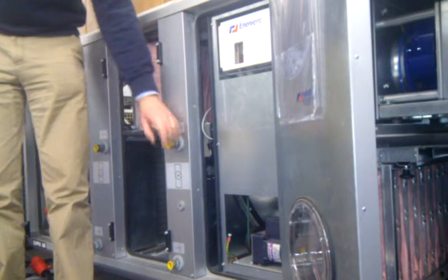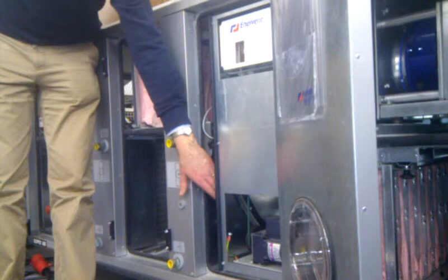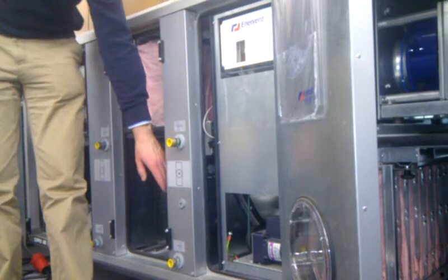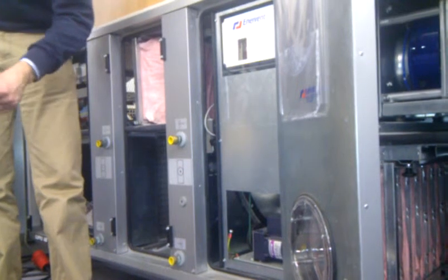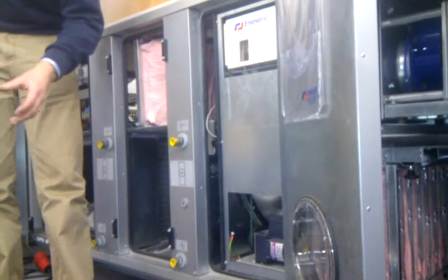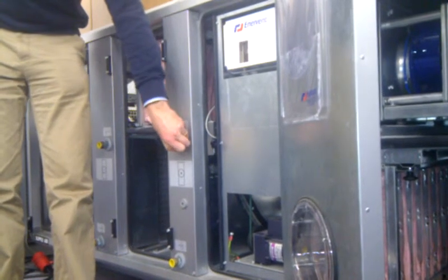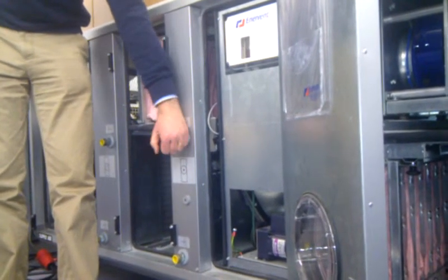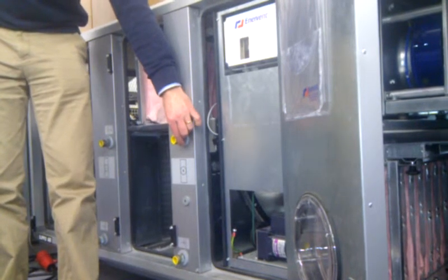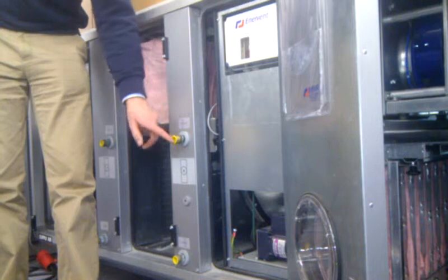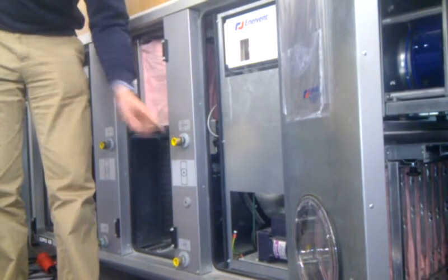Now, if I know the temperature here that I want coming in, and I know the temperature out there, I can do like we did last week, Q equals MCp delta T, the Cp for air being 1.02. Now I know my Q, my number of kilowatts of heating that I need. I can now do Q equals MCp delta T and solve for M on the water side, using Cp of 4.2 for the water, and tell me how many litres per second. This is what I was at last week.